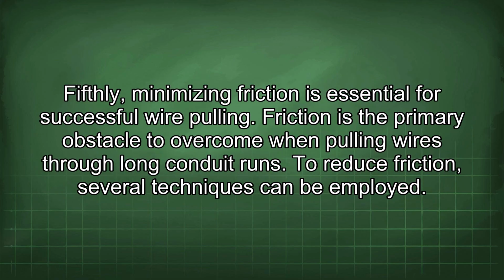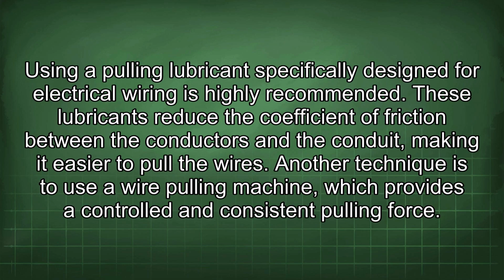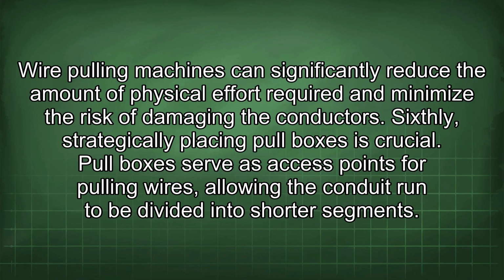Fifthly, minimizing friction is essential for successful wire pulling. Friction is the primary obstacle to overcome when pulling wires through long conduit runs. To reduce friction, several techniques can be employed. Using a pulling lubricant specifically designed for electrical wiring is highly recommended. These lubricants reduce the coefficient of friction between the conductors and the conduit, making it easier to pull the wires. Another technique is to use a wire pulling machine, which provides a controlled and consistent pulling force. Wire pulling machines can significantly reduce the amount of physical effort required and minimize the risk of damaging the conductors.